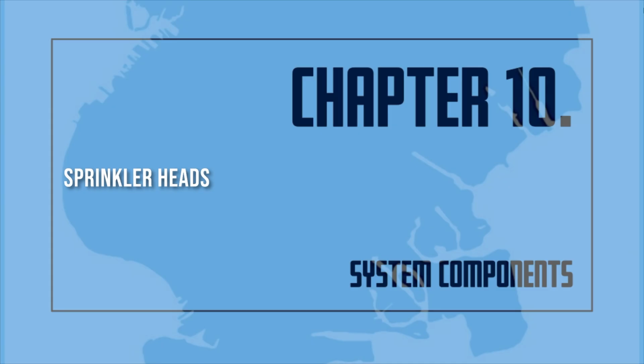A sprinkler head that has been recalled is called the cycling sprinkler. This sprinkler cycles water on and off depending on the temperature. When the disc reaches a temperature of 165 degrees Fahrenheit, the valve opens, permitting water to flow. When the disc temperature cools, the valve closes to shut off the water. These sprinklers and others listed for recall are subject to replacement, and can be found at www.cpsc.gov. Some sprinkler heads are designed to be used in special situations.